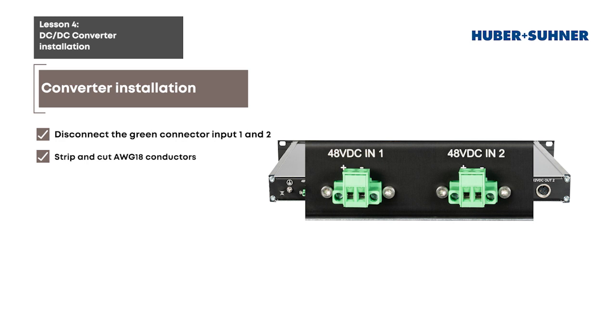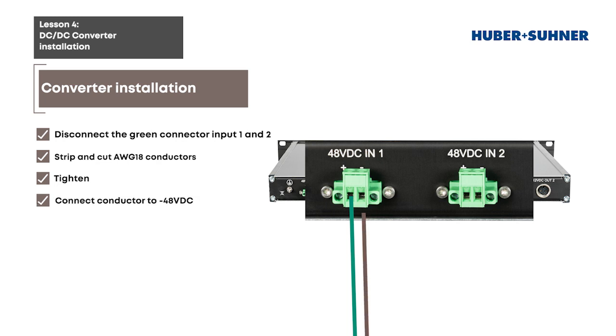Strip and cut AWG18 conductors in the terminals of the green connectors and tighten with a screwdriver to a torque of 4.42 to 5.3 pound-inches, or 0.5 to 0.6 Newton meters. Connect the conductor to negative 48 volts DC circuit with a minimum current rating of 10A. Ensure positive and negative terminals are not inverted.